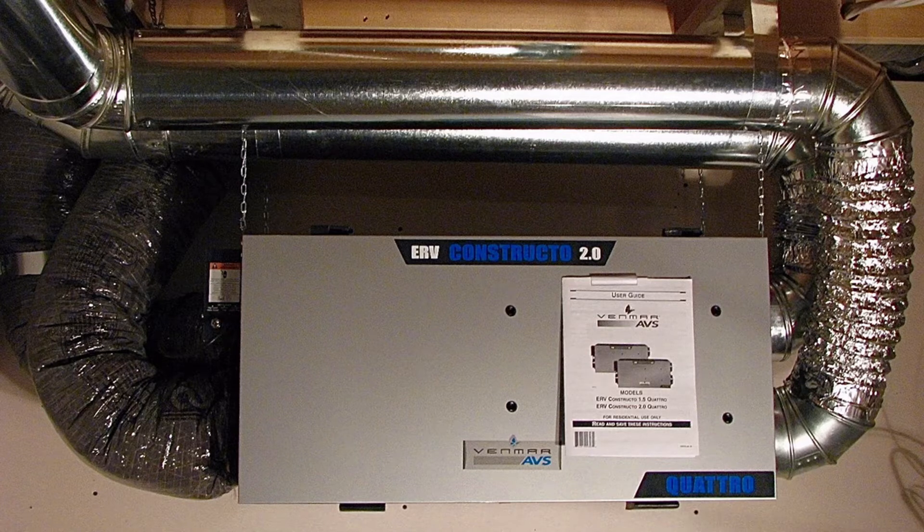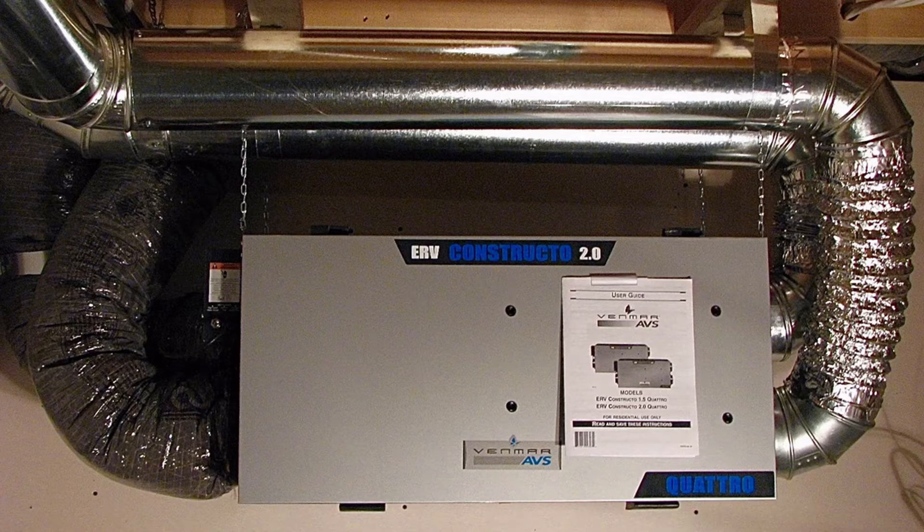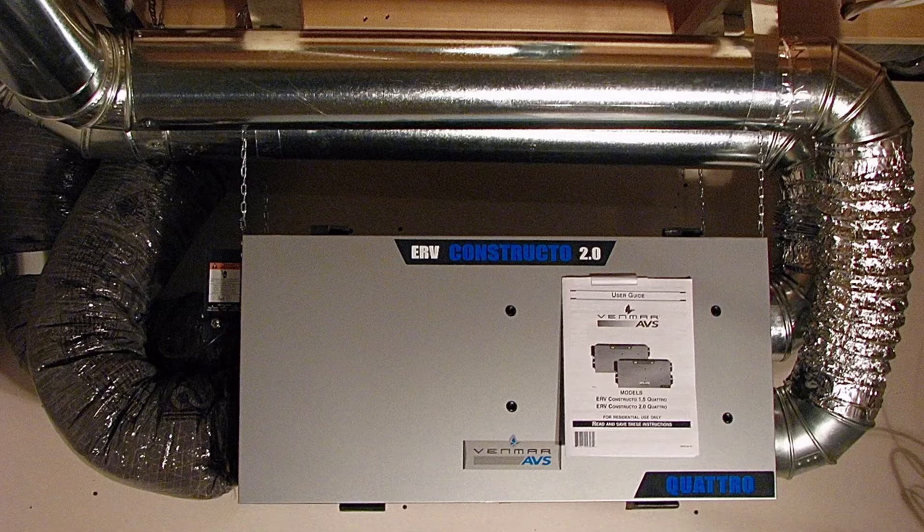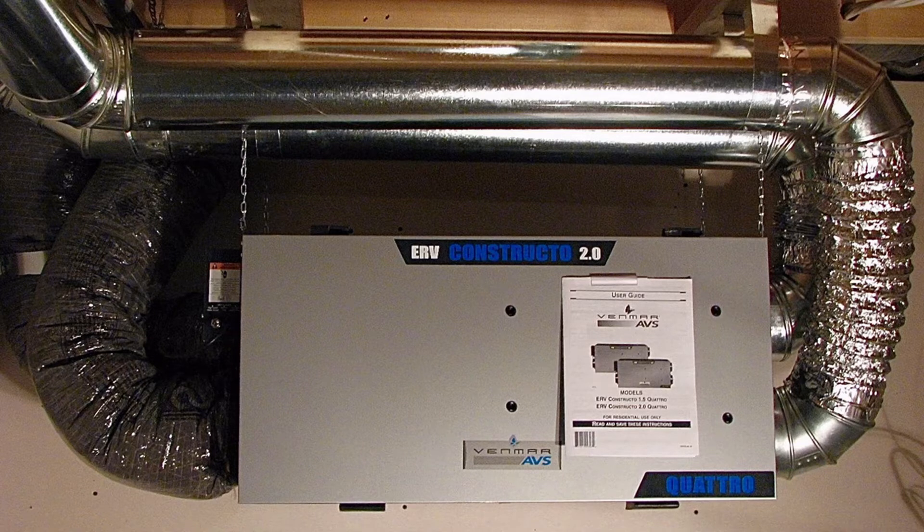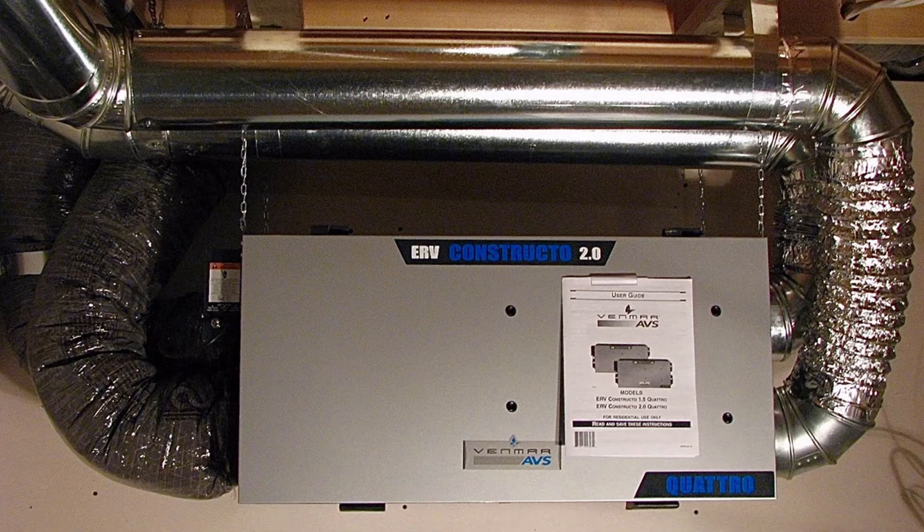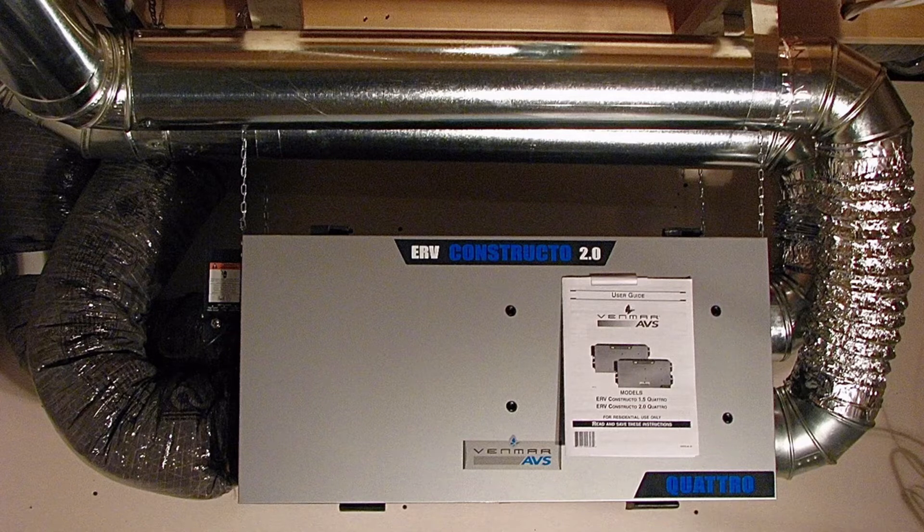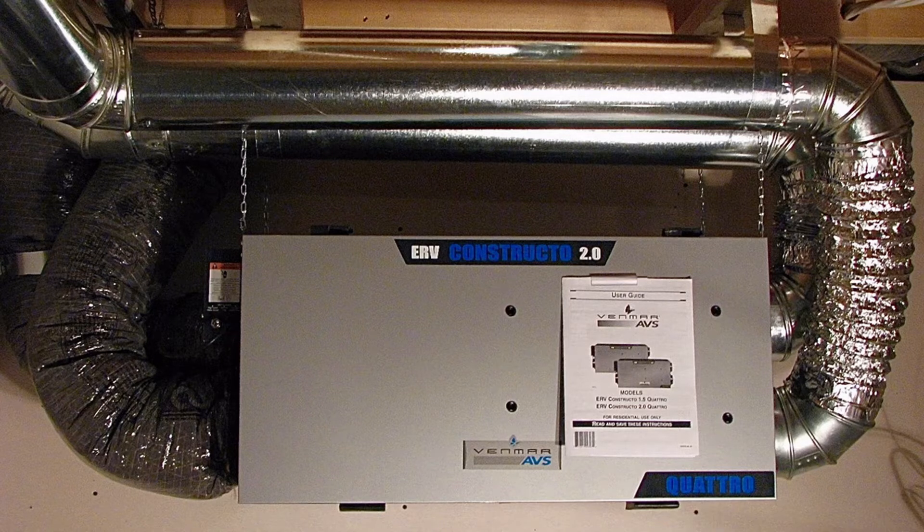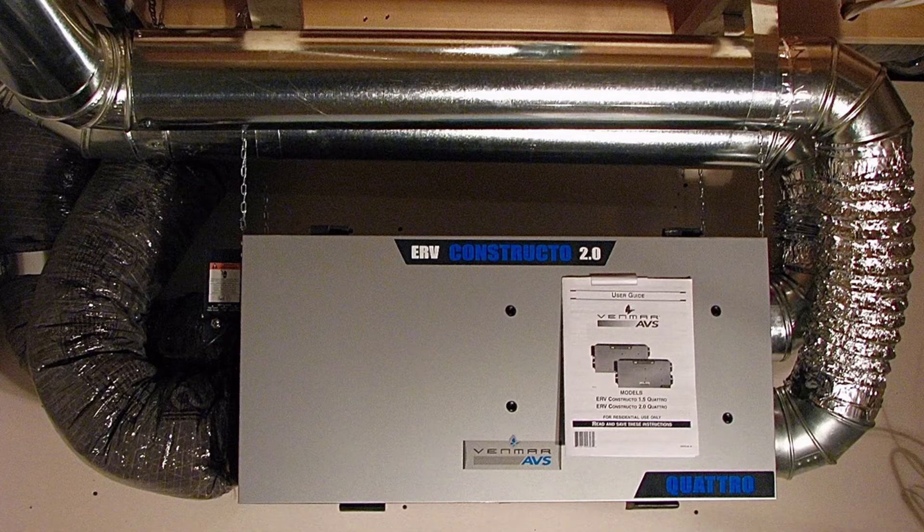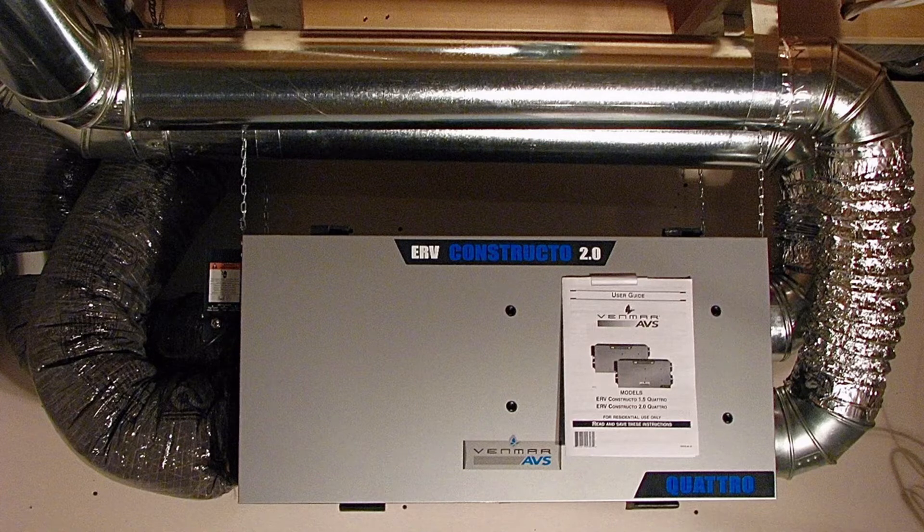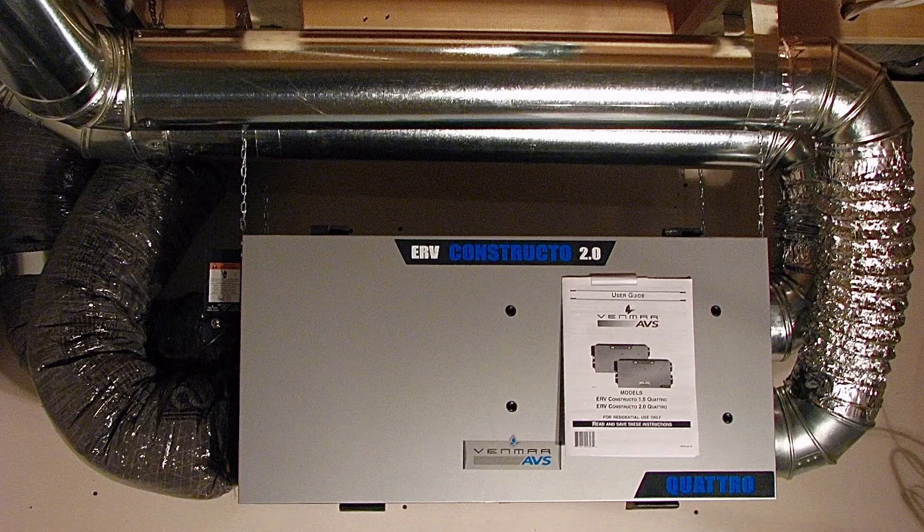New buildings will always require a ventilation checklist at the Pre-Drywall stage and at the final stage. Existing homes typically will not need these checklists submitted unless it's a full-gut project and a reinstallation of a mechanical system in its entirety. If all you're doing is replacing something like a bath fan, you do not need to submit these checklists.